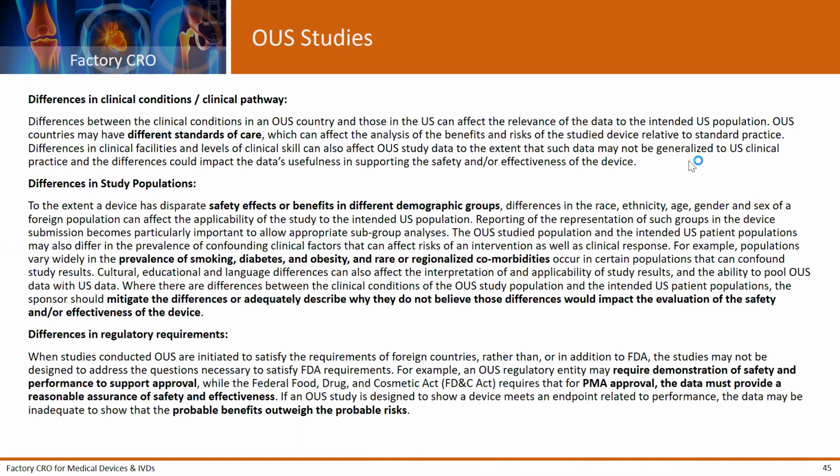If it says PMA, it would be a PMA submission. If it says 510K, it would be a 510K submission. But as Neil said, 65% of those are 510K exempt. And the FDA just recently released a fairly long list of product codes that they've newly made exempt because they're trying to streamline the process and downregulate devices that have shown a really great long-term history of safety.